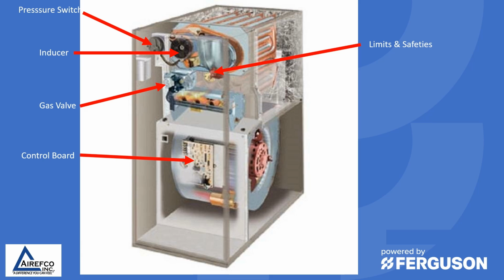Limits and safeties are seen by homeowners and some technicians as a nuisance, but these switches and safeties are designed to protect the furnace and protect the people that reside in the home that the furnace provides heat to. So whenever limits and safeties are tripping, there usually is a problem that you need to investigate and find out why this is happening and fix it.